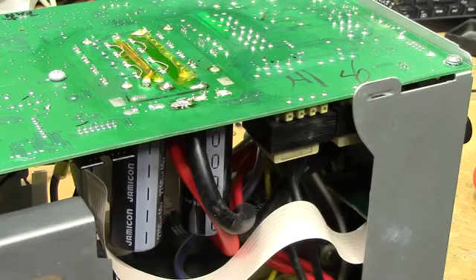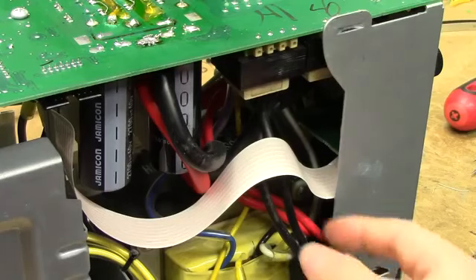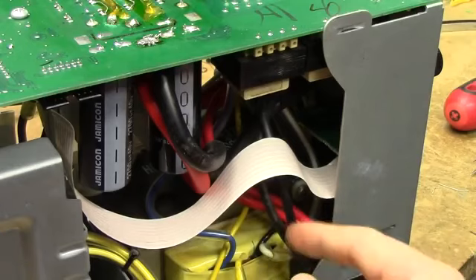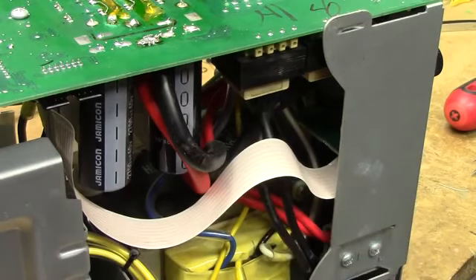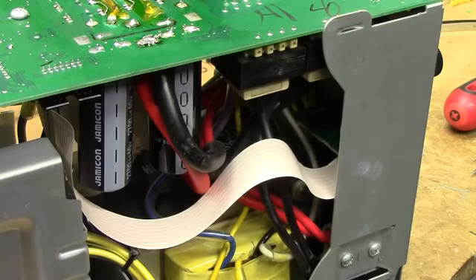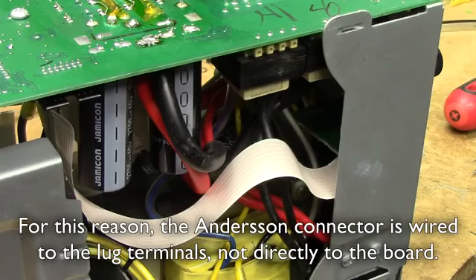The wiring I used for the DC input is 16 square millimeters, which should be good to just over 80 amps. Since it is fan cooled, it'll do the 100-ish amps it draws without any major issues. But really this, it's a bit on the low side. The Anderson connector on the back is just one which came from some unit stock, which has, I believe, dual 6 square millimeter wire coming out of it, which is really too thin to take the whole load of the unit. What I've actually used the Anderson connector for has been to connect a large 45,000 microfarad capacitor to it in order to reduce the ripple.